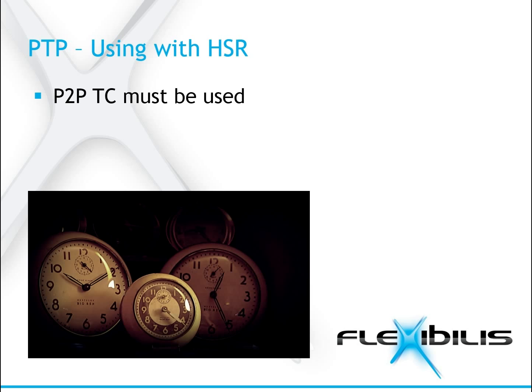With typical HSR networks, peer-to-peer transparent clocks have to be used instead of end-to-end transparent clocks. This is because there are more than one different routes the messages can travel, and in end-to-end mode the delay cannot be calculated separately for all the different routes. So if PTP is to be used in an HSR network, all nodes must have peer-to-peer transparent clocks. Two-step clock, which uses a separate follow-up message after the sync message, doesn't work if there is more than one ring in the network. The reason follow-up messages cannot be used is because there are several different routes for messages to take, and the receiver has no way to know which follow-up messages correspond to which event messages.